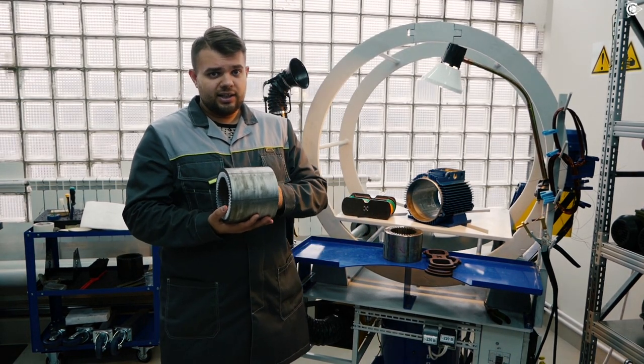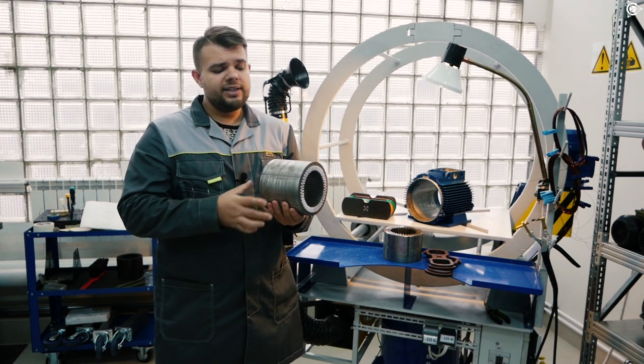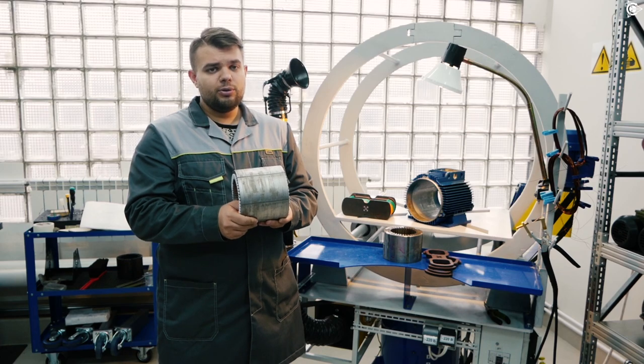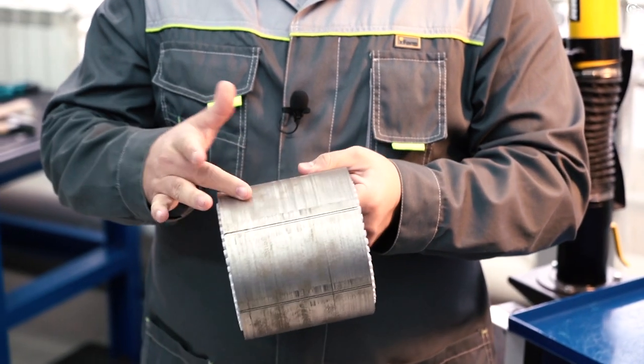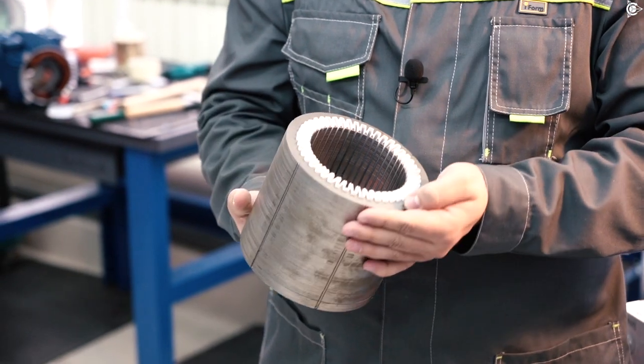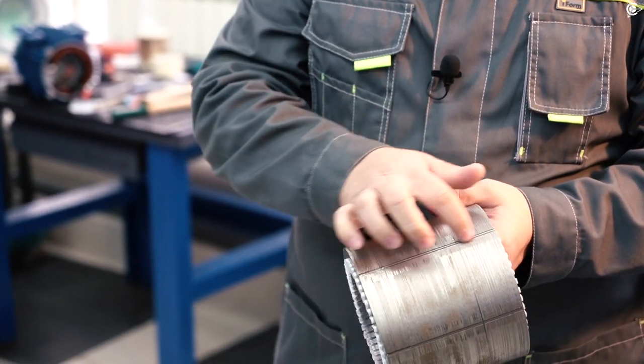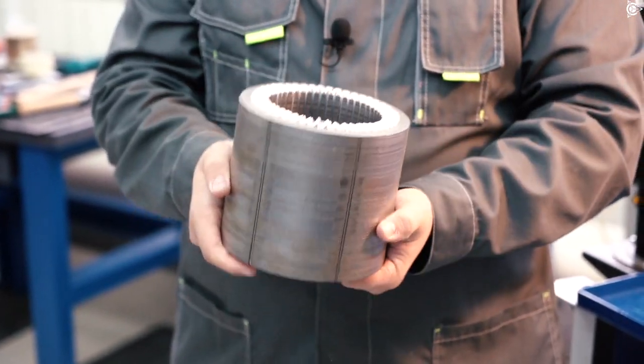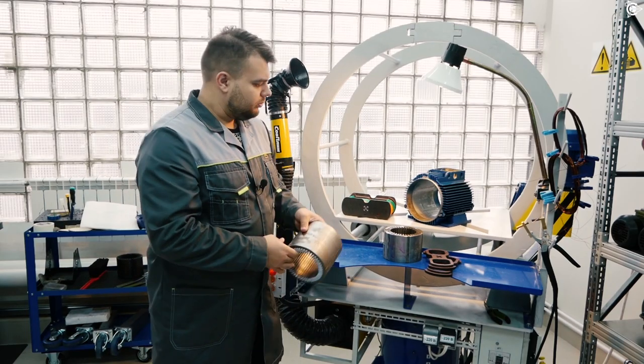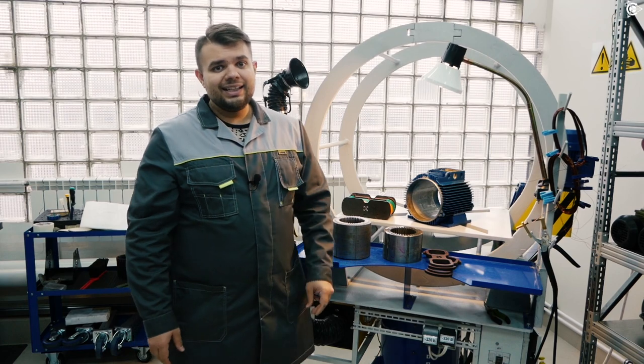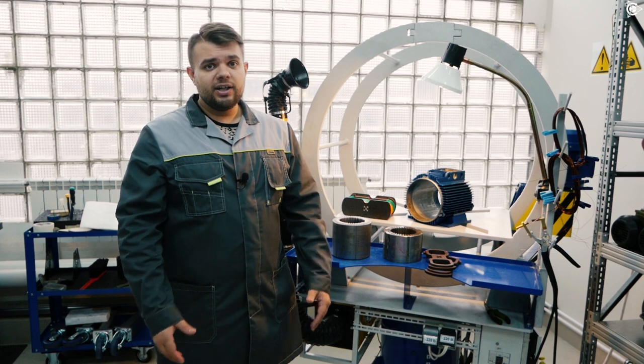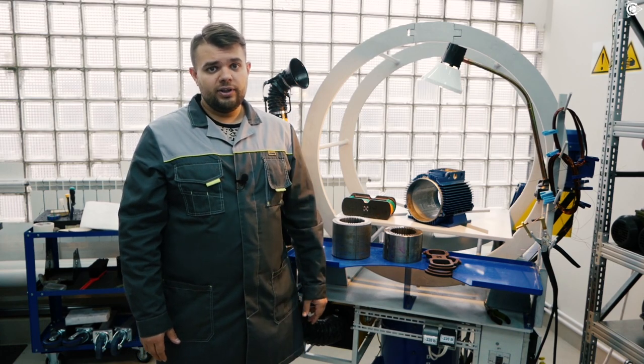You have already seen the stator pack of a standard motor. And now pay attention to the stator pack that has been produced using the laser equipment on the territory of Savalmash. The pack is more even, it's not deformed, there are no indentations. The welding line looks very neat and, as a matter of fact, all of these make one complete integral unit on the surface. It means we will not get any unexpected or adverse changes of electromagnetic field that appears as a result of any induction electric motor operation.